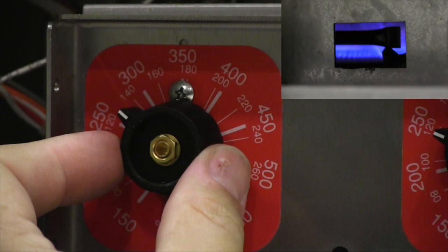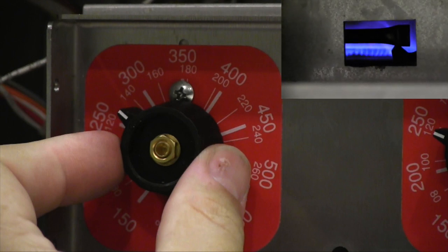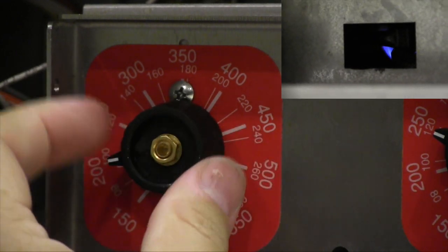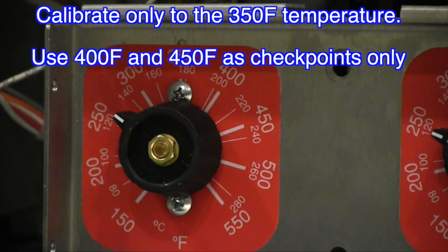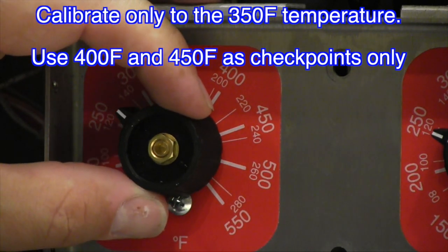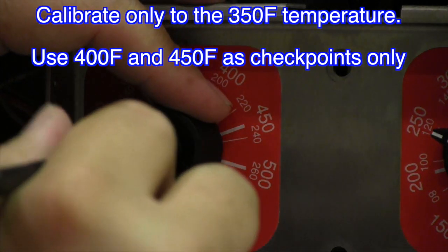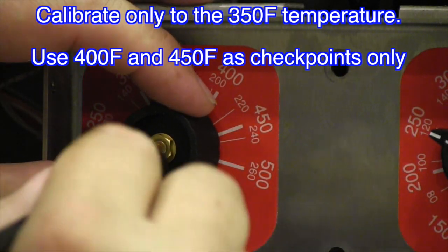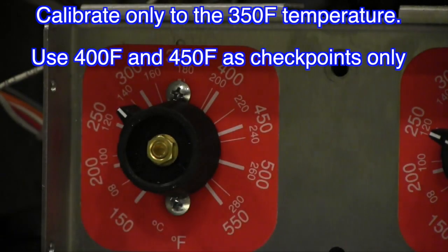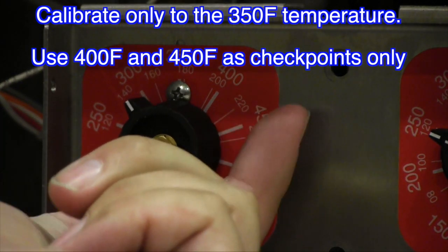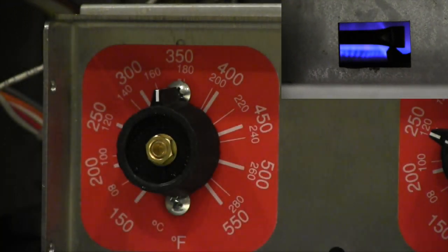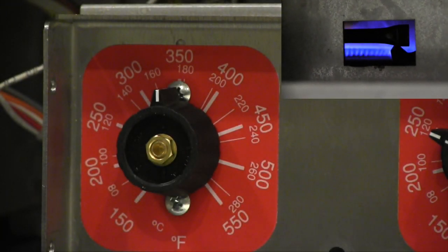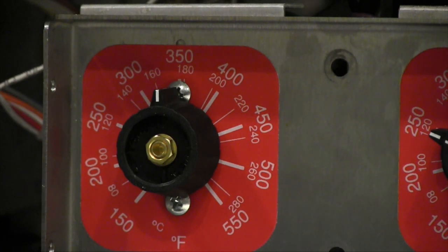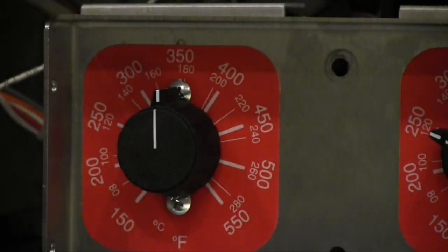If the burner does not turn on at the correct temperature, remove the black cap from the knob. Hold the knob tight and use a 5/16" nut driver to loosen the nut under the cap. Rotate the knob so that the pointer points at the desired temperature and retighten the nut. Once you get the knob set correctly, replace the cap, making sure the white lines are aligned with each other.